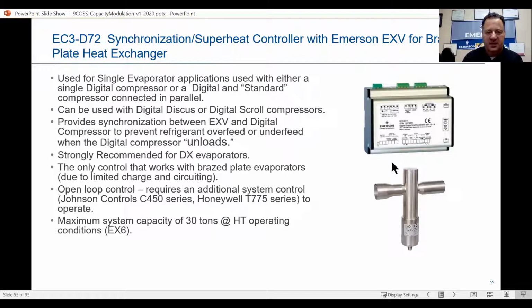Highly recommend this. In fact, it's a must. Strongly recommended for DX evaporators. The only controller that works with the braze plate evaporators due to limited charge and circuiting. Open loop controller requires an additional system controller, for example, Johnson Controls C450 series or the Honeywell T775 series, to operate. The maximum system capacity of this type of system is 30 tons at HT operating conditions for the EX6.